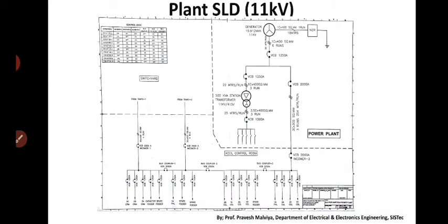Now one more thing is very important. This power plant itself is isolated, and this substation is also isolated from this power plant. But this 11 kV common bus has to be charged, and all these circuit breakers, all these bus coupler panels, have to be closed. So it was a challenge for us to synchronize this power plant with this substation's electrical parameters.